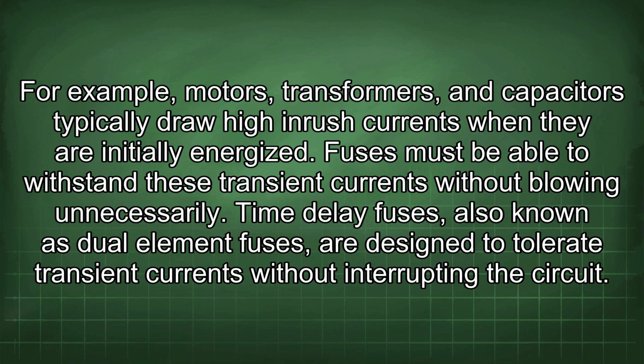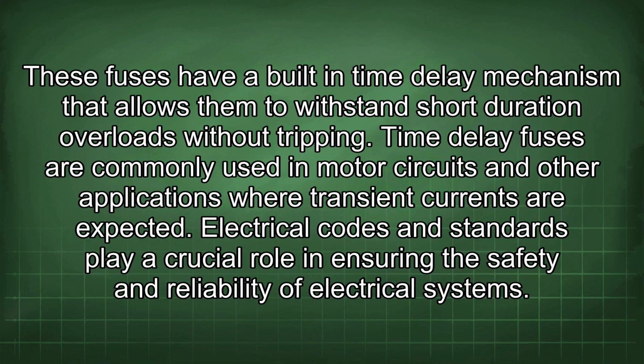Time delay fuses, also known as dual-element fuses, are designed to tolerate transient currents without interrupting the circuit. These fuses have a built-in time delay mechanism that allows them to withstand short-duration overloads without tripping. Time delay fuses are commonly used in motor circuits and other applications where transient currents are expected.